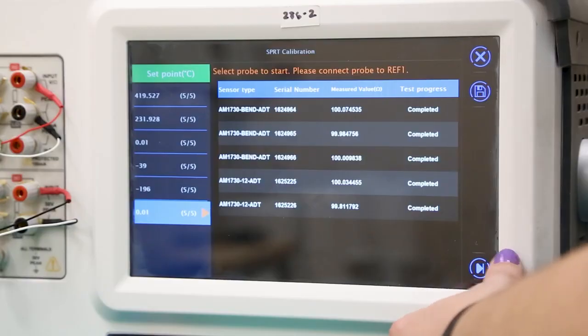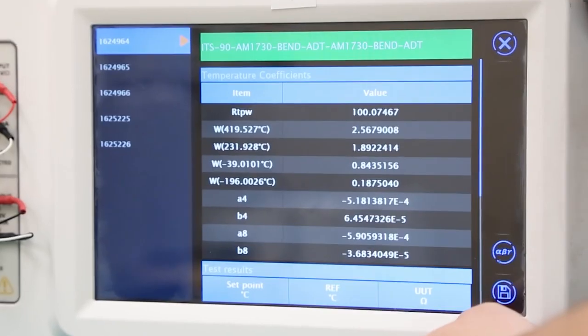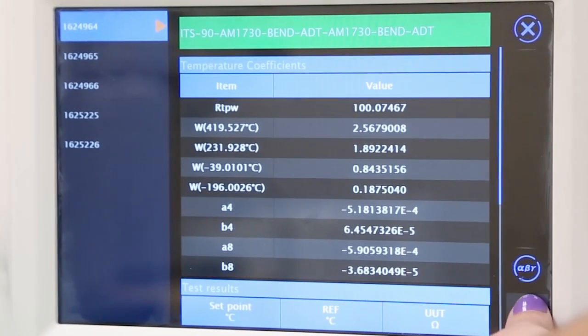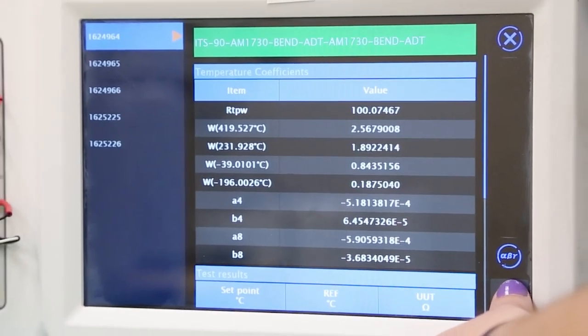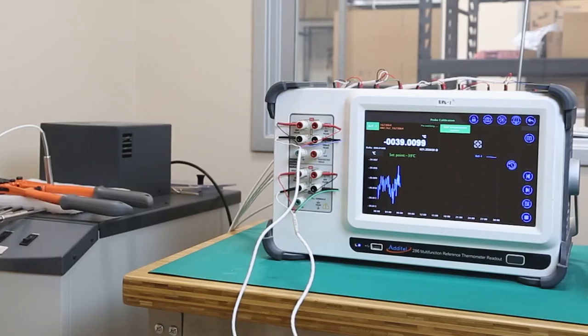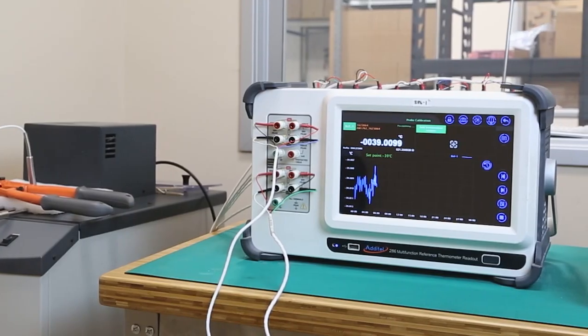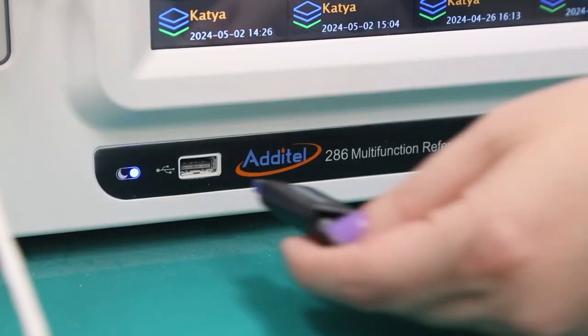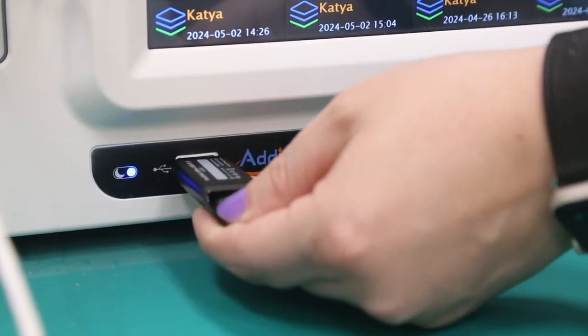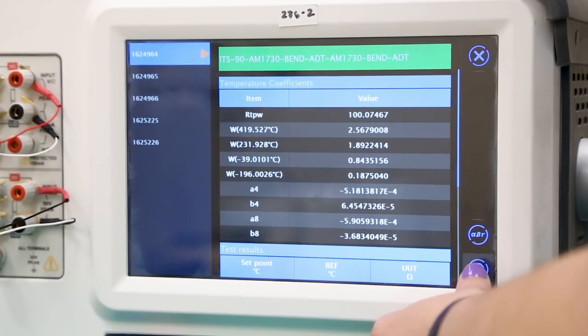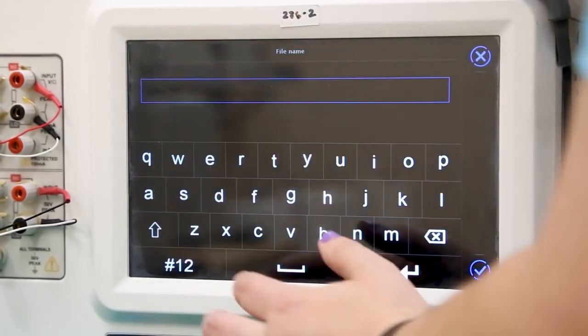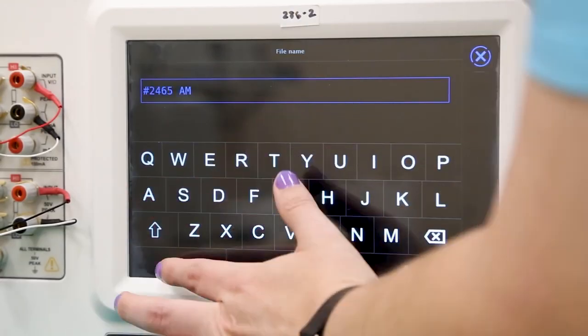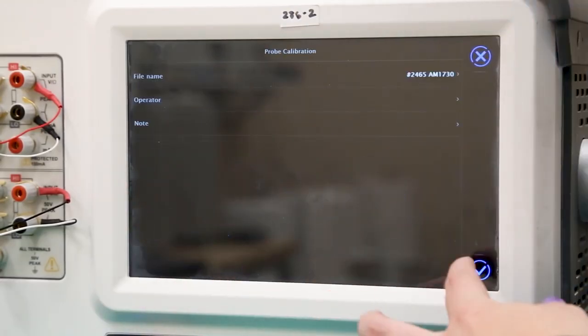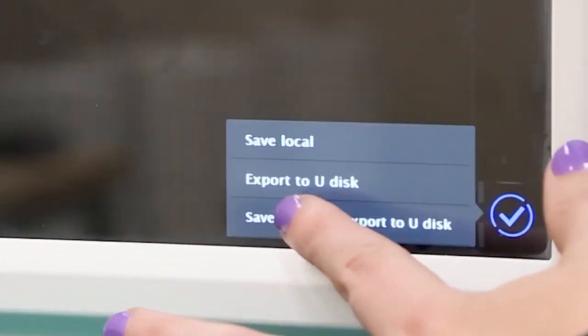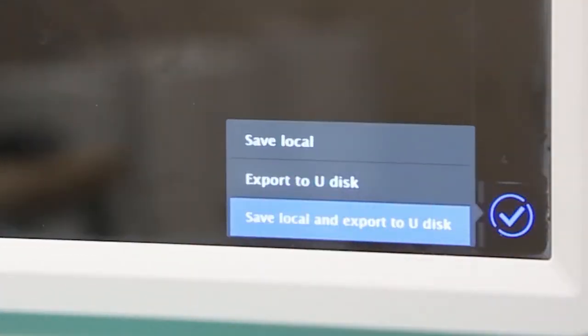Once all testing is complete, calibration results can be saved and reviewed immediately. The Additel 286 automatically calculates resistance ratios, ITS-90 temperature coefficients, temperature averages, and more, making it one of the most intuitive and easy to use electrical bridges on the market. These results can then be saved and exported by first inserting a USB drive, then pressing the next arrow in the bottom right. Here the user can enter the file name, the operator name, and any extra notes about the procedure, before exporting by selecting the Save Local and Export to UDisk option in the bottom right corner.